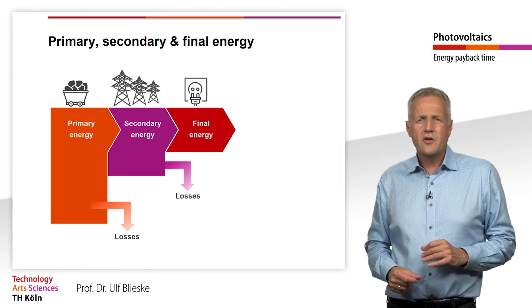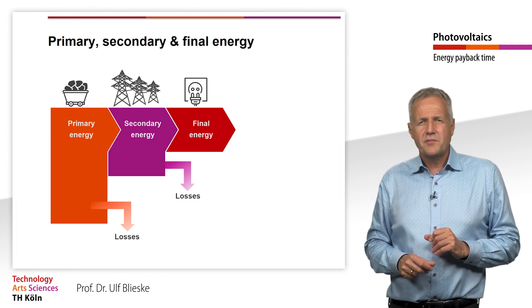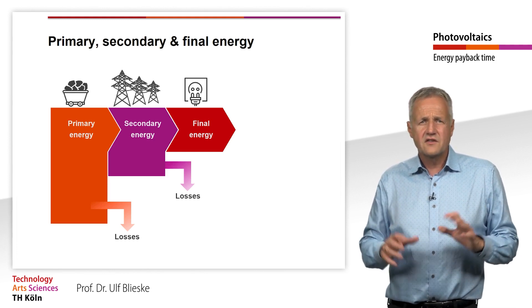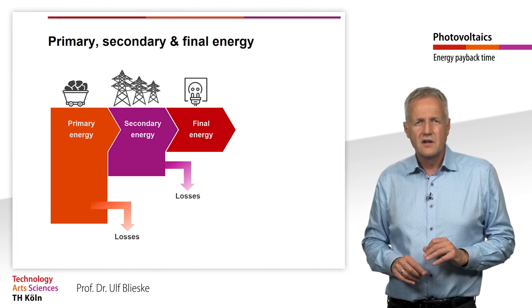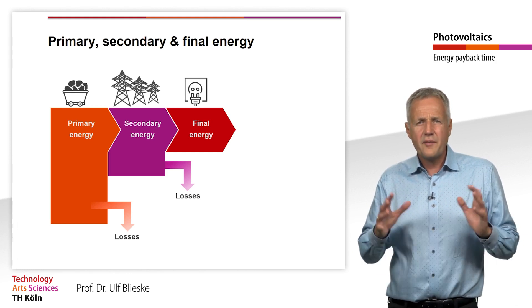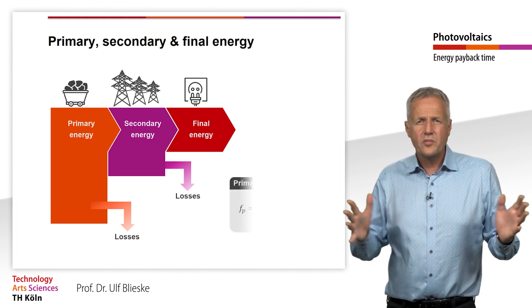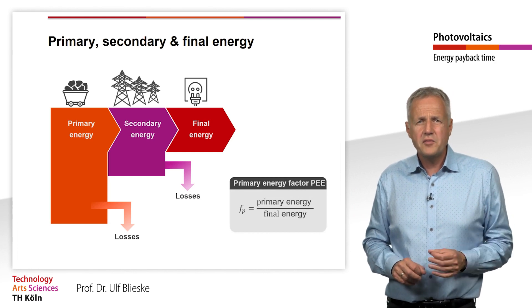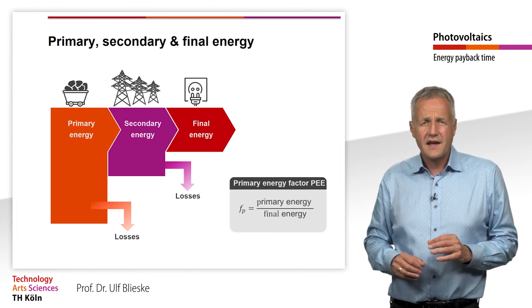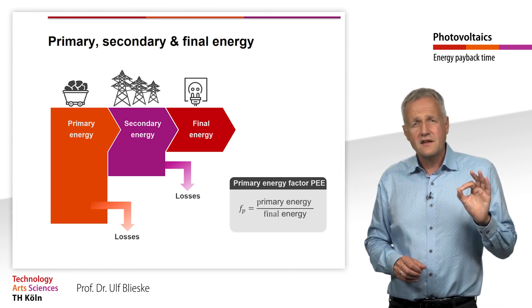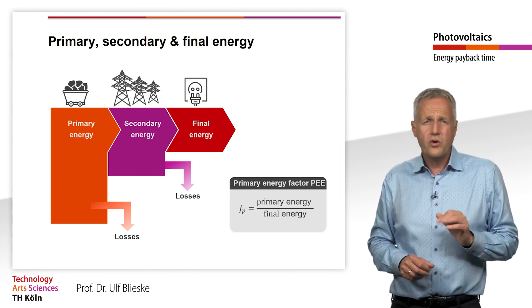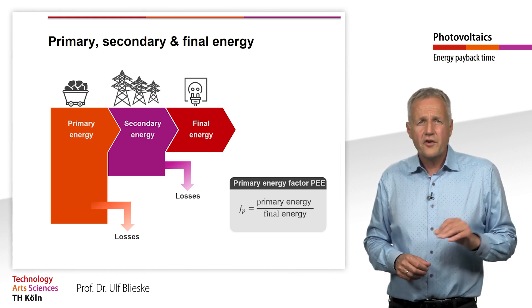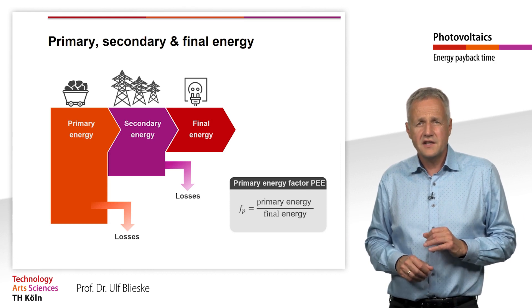In order to obtain comparable results when creating an energy balance, the final energy is first converted into its primary energy equivalent. To do this, we define the primary energy factor Fp. This corresponds to the ratio of primary energy to the final energy. For example, the primary energy factor of the German electricity mix in 2022 is 2.5. This means for 1 kWh of electrical energy, 2.5 kWh of primary energy are needed.